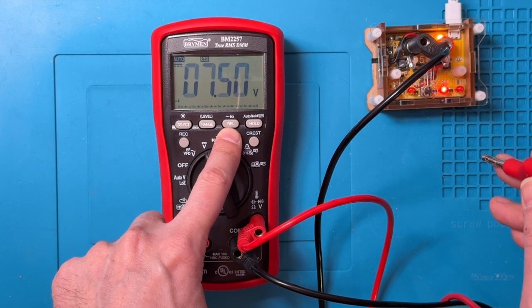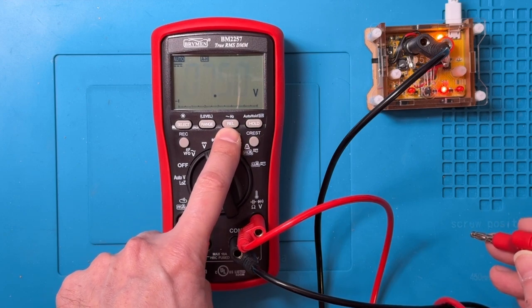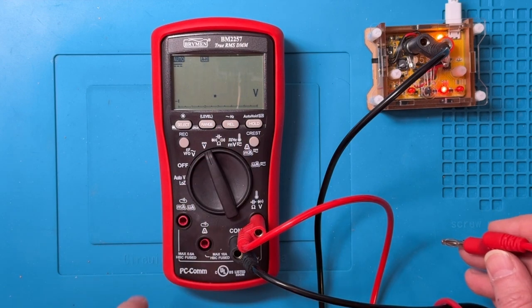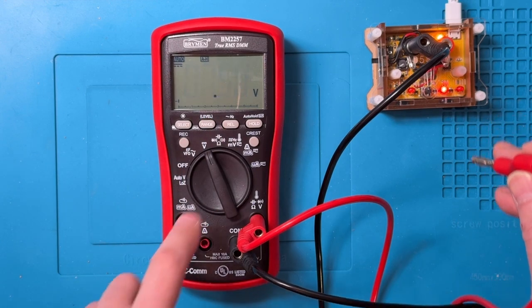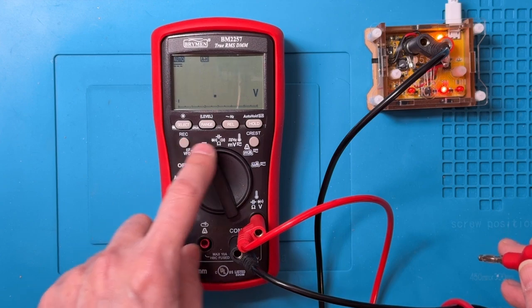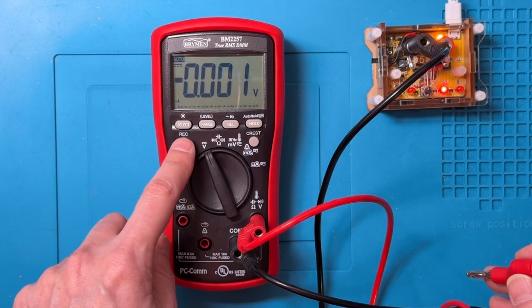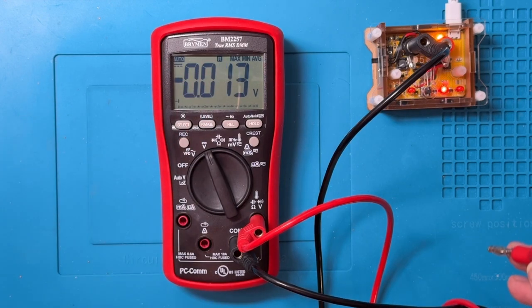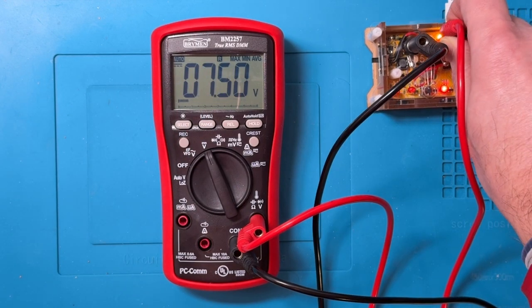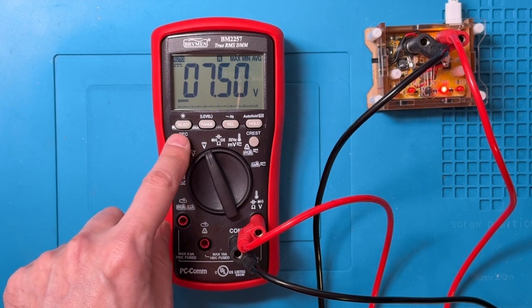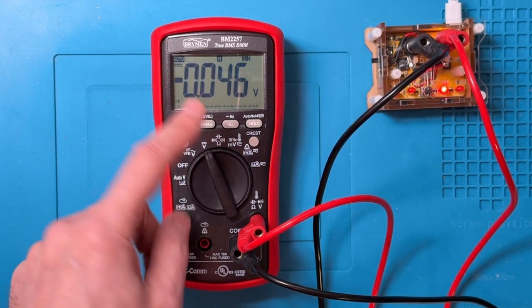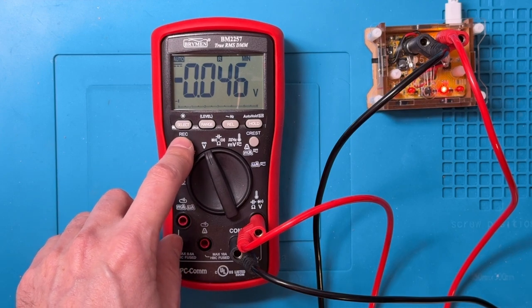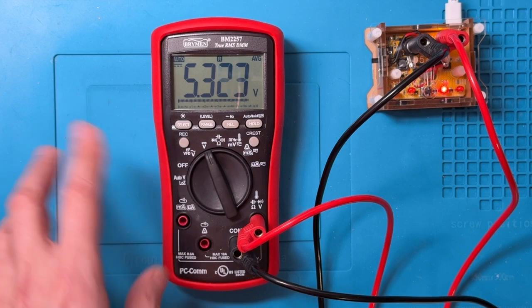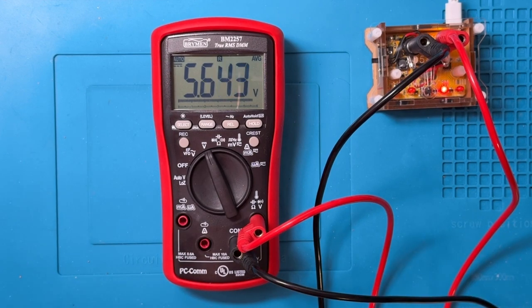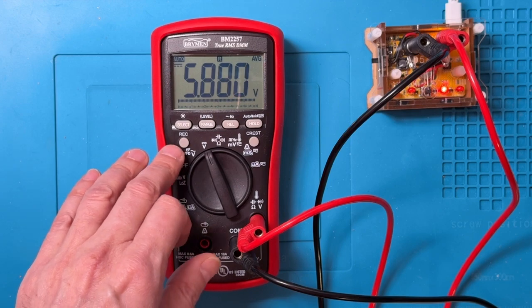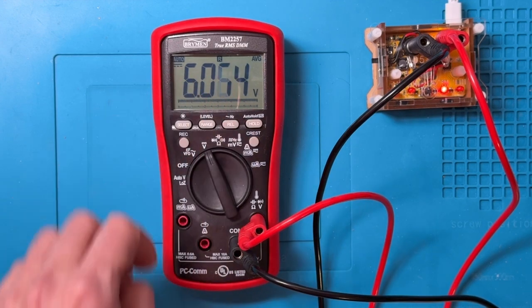There's also a relative feature, so you can do something like zero out the resistance of some probes if you have some probes with too high a resistance. There is a min-max averaging feature, so I'm just going to leave the auto hold here, turn that off. So I press that, and we see max min average there. And so if I connect that, by pressing this it'll tell me the max voltage, the min voltage. You can see that it was ranging because it wasn't connected the whole time. And then the average voltage, which will range because it's a cumulative average from the time in which you first entered the min-max average mode.